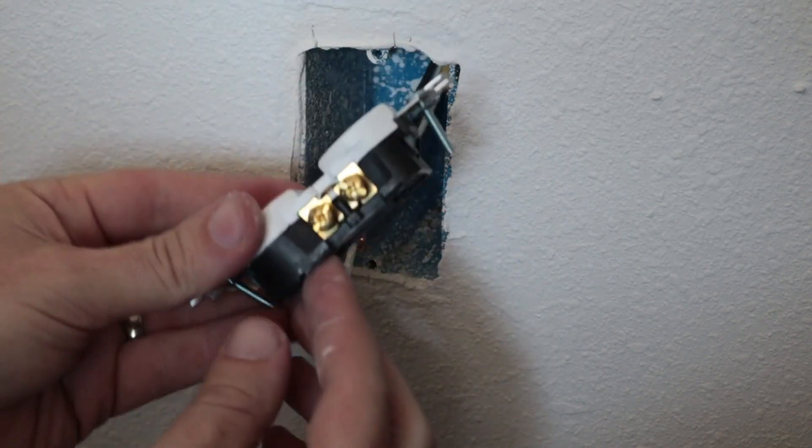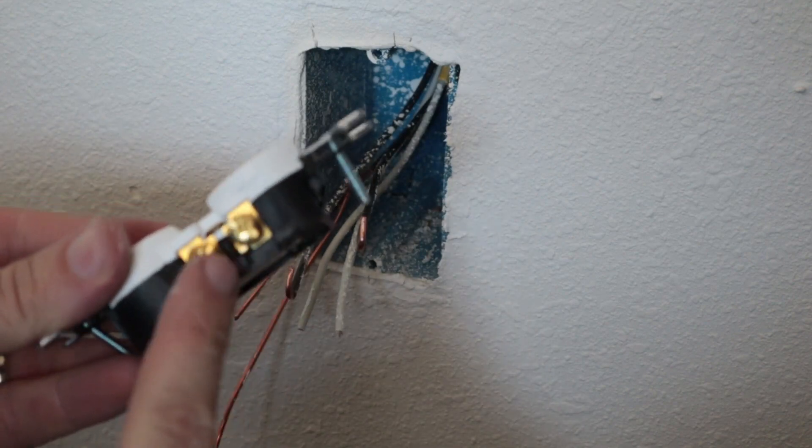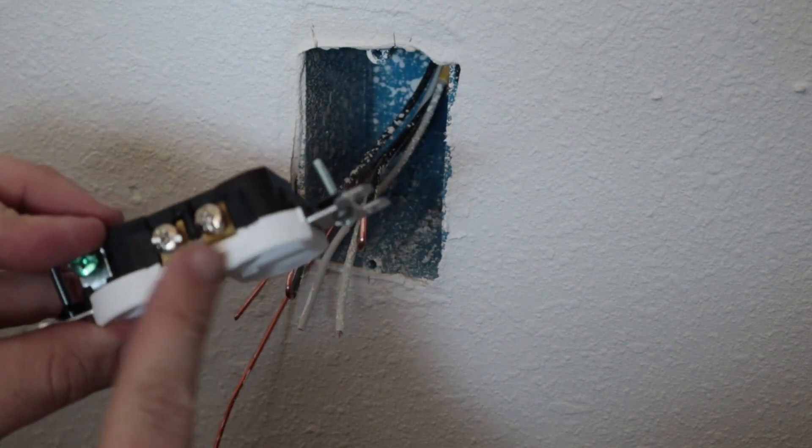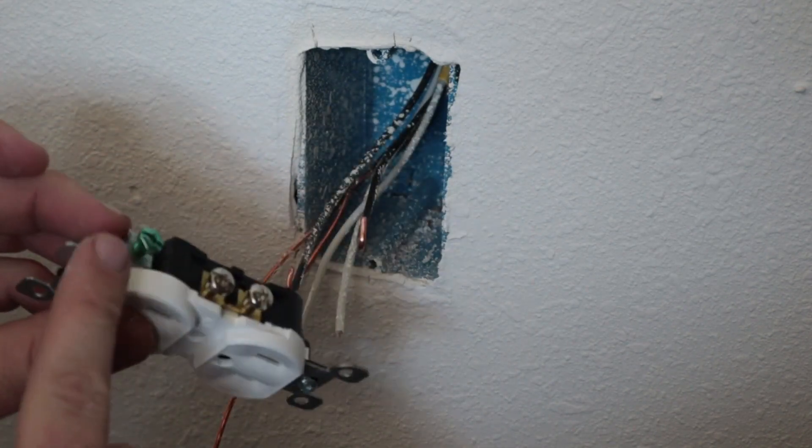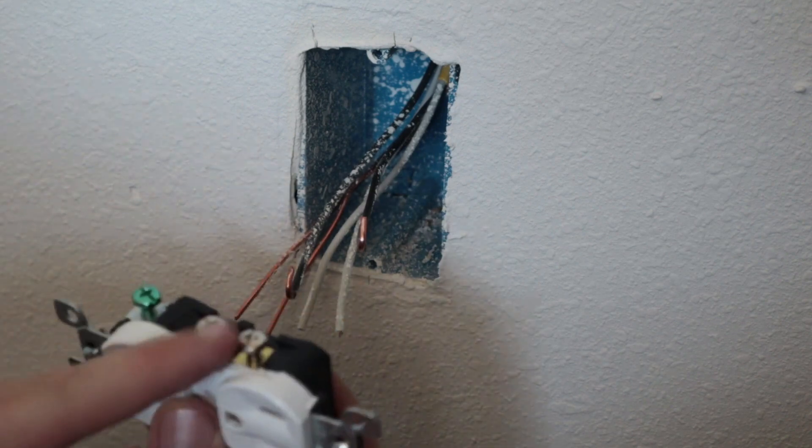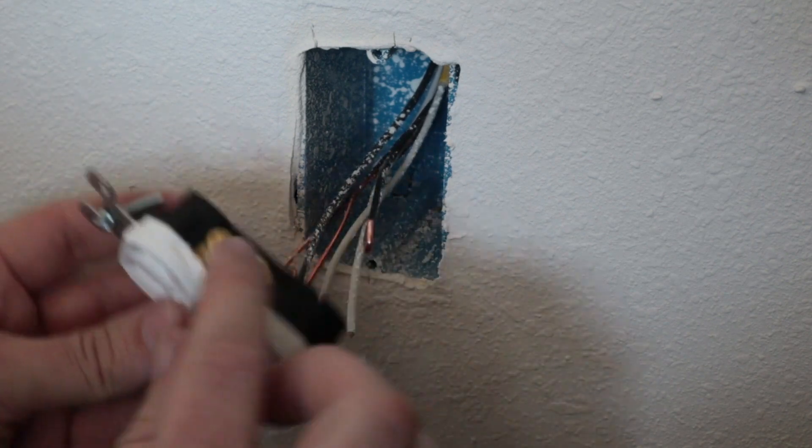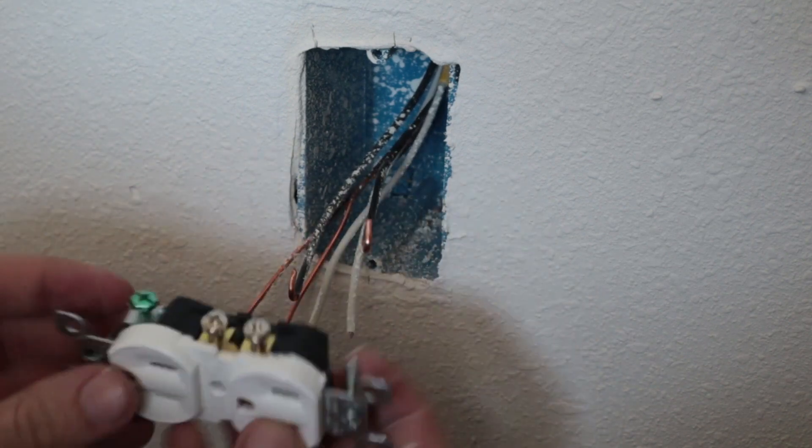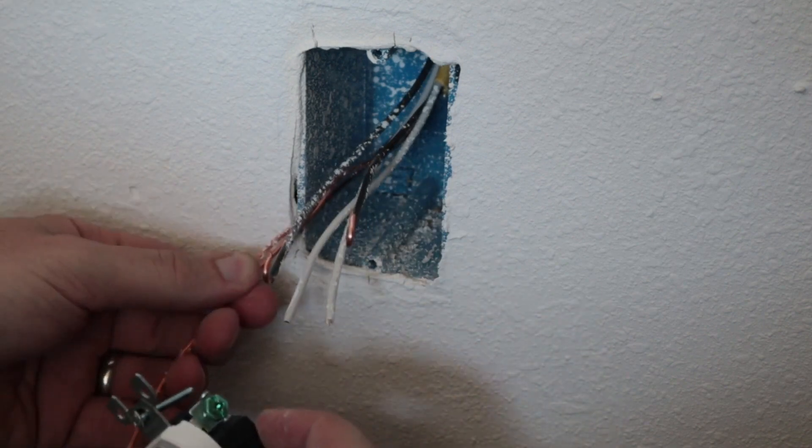Now the outlet has two sides. It has a copper screw and it has a silver screw, and then it has a green grounding screw. The silver screws are for the white wire. The copper screws are for the black wires. And the green screw is for these ones that are like copper looking wires.